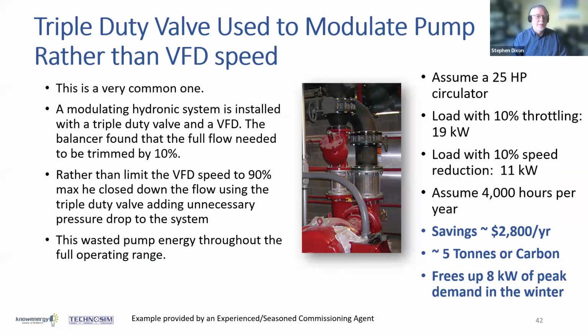Triple duty valves on pumps, right? This is a simple valve designed to modulate flow from a pump, and also to provide backflow prevention. Oftentimes they're used to permanently reduce the flow from a pump. This was a system where a variable speed drive actually existed and was running full speed, and somebody used the valve to turn it down instead. So whenever we walk into a mechanical room, we always go looking for those triple duty valves, to see if there's an opportunity to release that valve and use the drive elsewhere. That can contribute directly to carbon reduction and cost reduction as well.